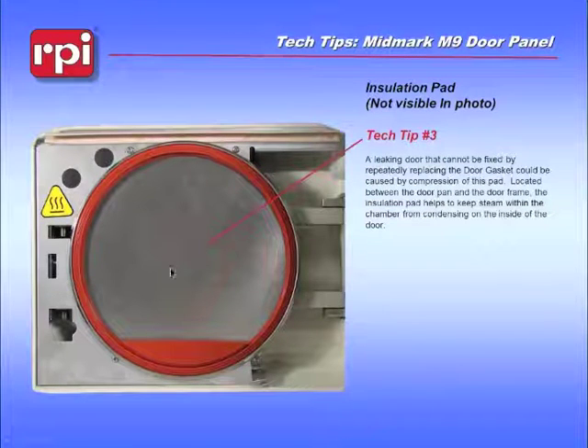One thing about replacing this insulation pad, you have to remove the plastic frame of the door and this metal plate, and there is a welded stud on the back of this door assembly. And be very careful when tightening the nut that holds that stud in place. You don't want to unweld it from the door. That cannot be repaired.